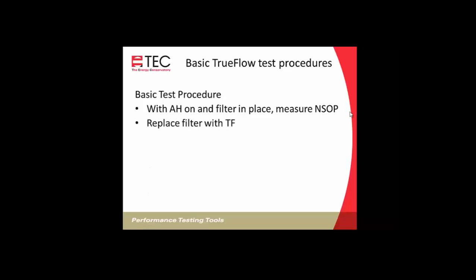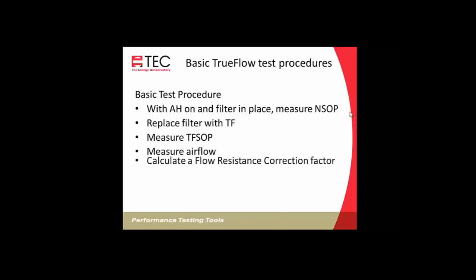And we'll replace the filter with the true flow, and then we'll measure the true flow system operating pressure, which is likely to be different than the normal system operating pressure. The filter may be more restrictive, or the true flow may be more restrictive, but they're likely to be a different number. And if the pressure is the same, the flow is the same, so we need to make an adjustment. Then we'll measure the airflow next, is the next step, and then calculate the flow resistance correction factor.